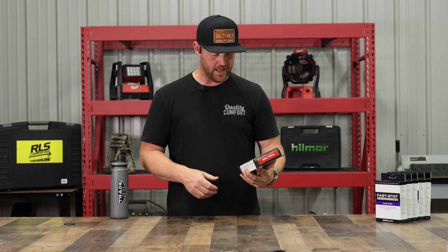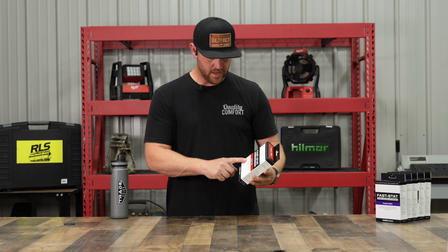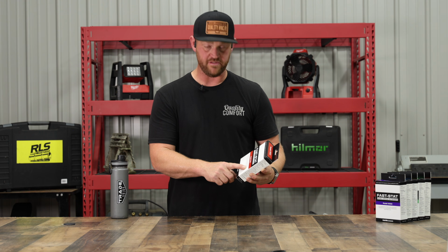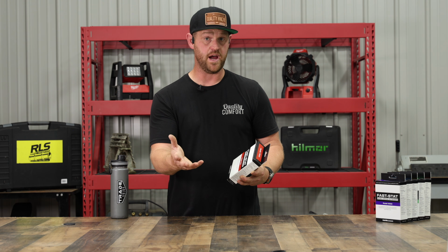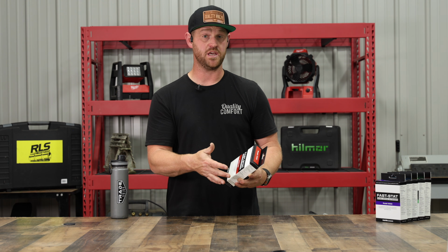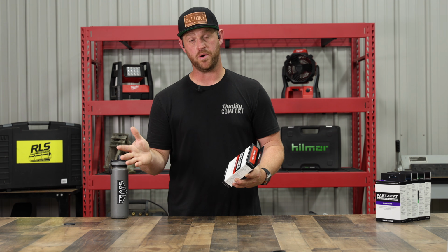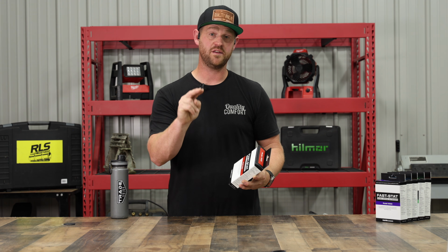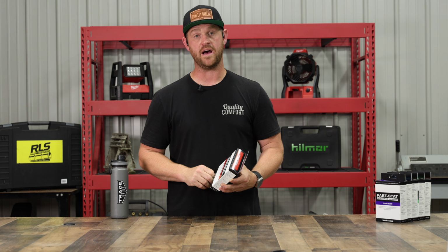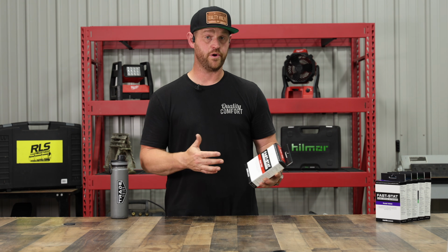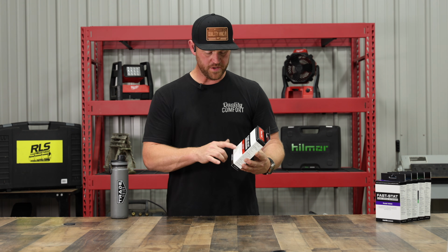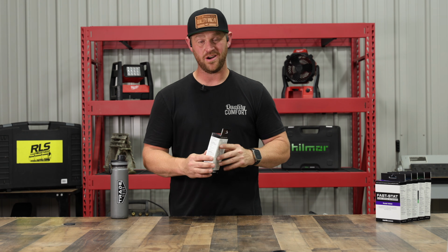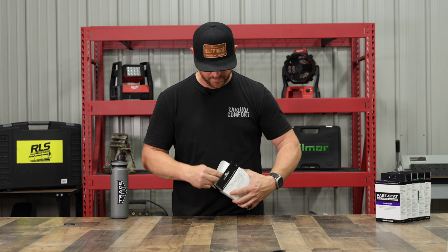For example, this model 7000, they say it's an air conditioner to heat pump conversion. So that's a thing, right? A lot of people might have straight AC units, but they want to convert to a heat pump, and they only have two conductors on that low volt cable going outside. Of course, we are referring to split systems here. Well, what this can do, this has a sender and a receiver. I'll go ahead and open up the box real quick.